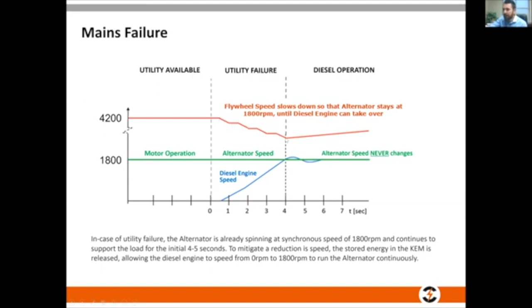So the amount of electromagnetic field is via a controlled DC current. That controlled DC current is fixed, and it allows us to perfectly control and to make sure we maintain our 1800 RPM. This 42 drops to 41, 40, 39, 38, whatever it is, until the engine takes over. So we're going to go back through. And you've seen this one line, you understand this. We've got our standard switchgear configuration, input-output bypass, very similar to a static UPS.